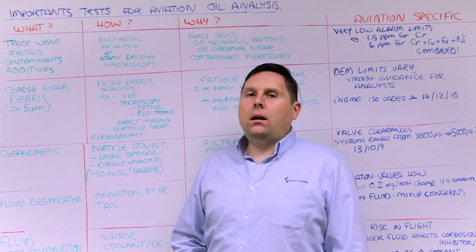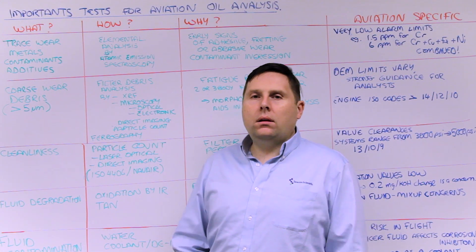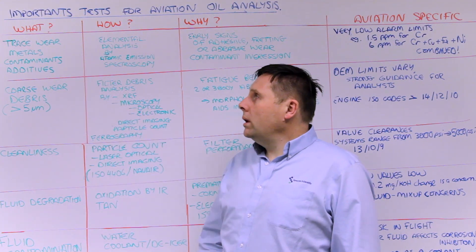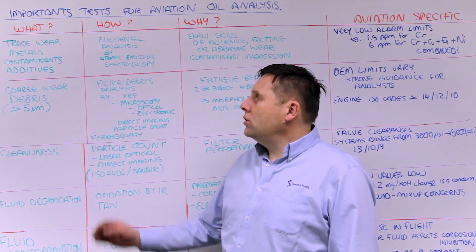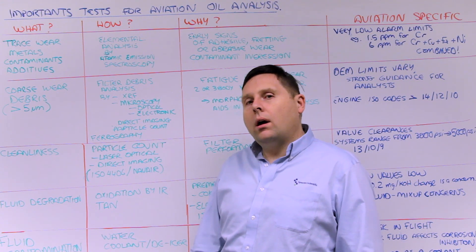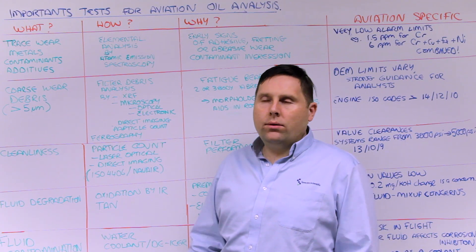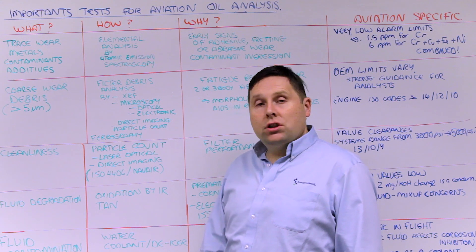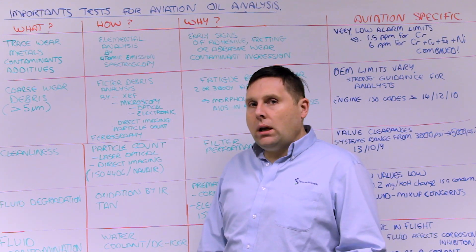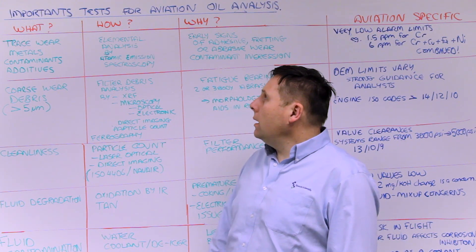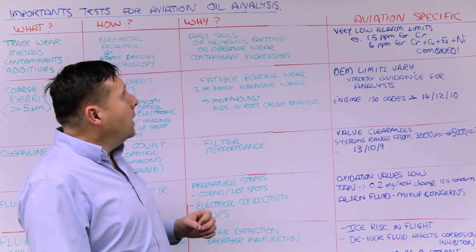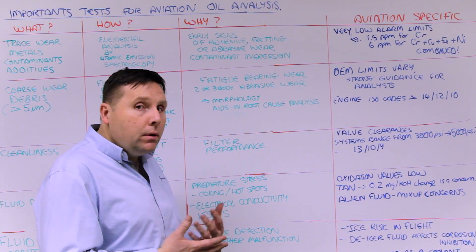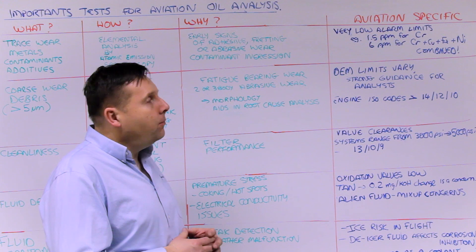What are the important tests in aviation oil analysis? One key thing we want to look for is trace wear metals, contaminants, and additives — these are tested throughout the entire industry. It's done by elemental analysis using atomic emission spectroscopy, such as RDE or ICP. This is important because it looks for early signs of adhesive, fretting, or abrasive wear, contaminant ingression, and can also assess the additive package in the oil.